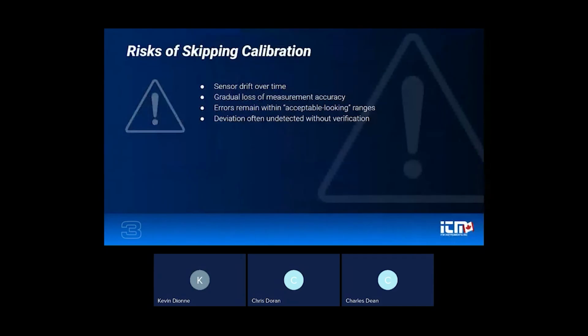So, the risks of skipping calibration. All pressure sensors experience drift over time. This drift can result from normal sensor aging, repeated pressure cycling, mechanical stress, and exposure to environmental conditions like we spoke about, vibration, moisture. As that drift occurs, there is a gradual loss of measurement accuracy. The change is typically incremental, not sudden, which makes it more difficult to recognize if you're not trained to. For lack of a better term, the reading values appear reasonable. Like they're not egregious and they're still within an acceptable range. And because there's no obvious failure or alarm, the instrument continues to be trusted.